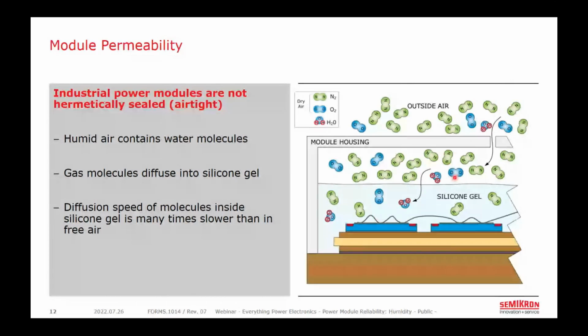I can't point to evidence of salinity or salts inside the module, but in theory it should be similar to another problem that we have that's not addressed in this presentation, which is corrosive environments with stuff like sulfur. So sulfur molecules in maybe wastewater treatment plants or paper pulp processing or things like that. The issue there is that in addition to water, you have sulfur molecules coming in as well, and those interact with the water and form very corrosive acids that corrode the copper and other conductors within here. So again, I'm not a chemist, but it's certainly possible.